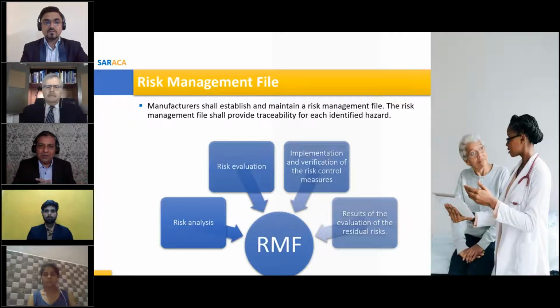Doing DFMEA is overwhelming for them. But it requires a lot of training and understanding that all the documents related to risk have to be put together in this file. When a notified body comes and asks you for the risk-related documentation, if you run around and cannot get them all together, you will definitely have an observation, if not a non-conformance. So it's very important that the risk management file is maintained rigorously and updated.